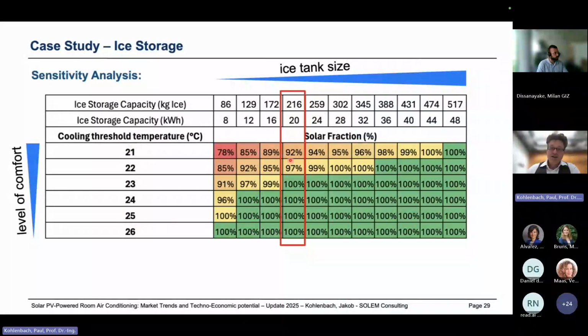Now what can we see? The 92%, the result from the previous slide, we find here in the cell. We can increase those 92% to 100 if we go further to the right, increasing the ice tank size, and with a big enough tank we can achieve 100%. On the opposite side, from the 92%, we can lower the level of comfort slightly and set the cooling threshold temperature to 23 degrees, which gives us 100% coverage of the annual building load.